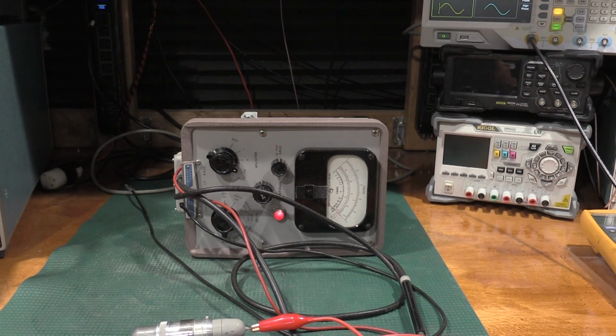There we go, and it's actually set pretty well. Now, this is not an ideal measurement. The meter's on its side, it's not in its case, it's not warmed up, so nowhere near ideal. But that tells me that the probe in the tube is working, which is fantastic.